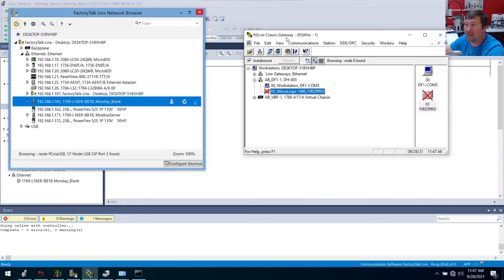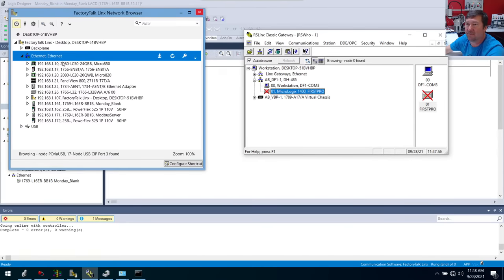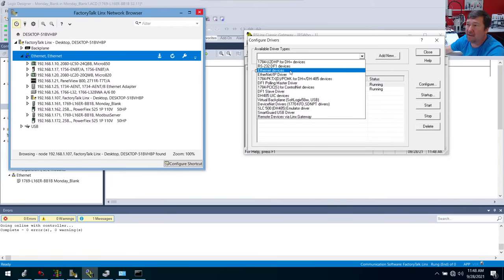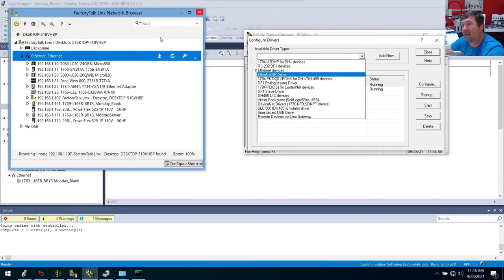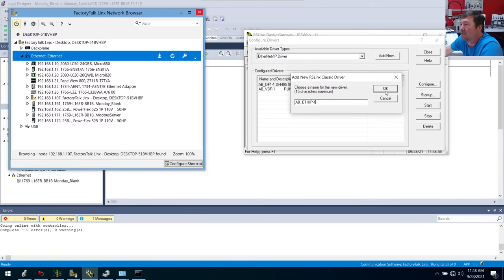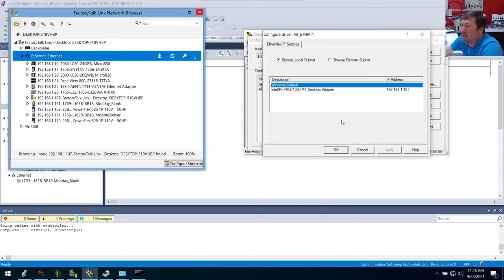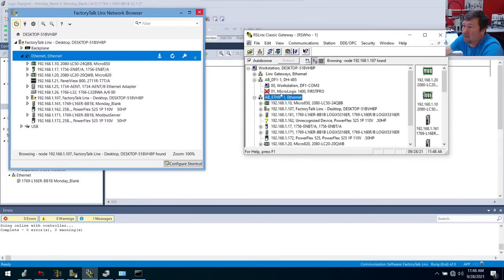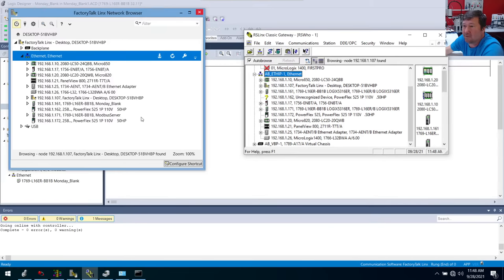One thing I didn't talk about there is we still have our RSLinx Classic over here. What's the equivalent of what we see in FactoryTalk vs. RSLinx? Because this is going to trip you up. Now we just have plain-jane Ethernet. But if we go over here, Communications, Configure Drivers, and our available driver types, we have two here: Ethernet Devices and Ethernet IP. The default Ethernet settings on FactoryTalk Linx is going to be this Ethernet IP driver. So I'm going to click Add New to it, and as much as I say make things memorable, this may be the one time I usually find people have a little less friction if I leave it at default. Then it's going to ask us which one — we ought to be able to leave it at Windows Default. Close, and now we can open up our Ethernet IP. This is identical to what we see in Factory Talk.